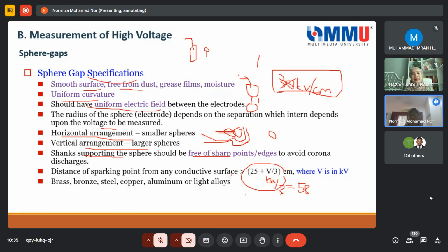So the distance of sparking point is the safety or clearance distance to be away from the equipment that is being injected. We normally use this formula, which is actually for the sphere gap. But for other equipment, they may also have another way or another formula to calculate it. But for the high voltage lab that we have at MMU, we use the common one, in other words, we just take 2 kV per cm for all equipment.